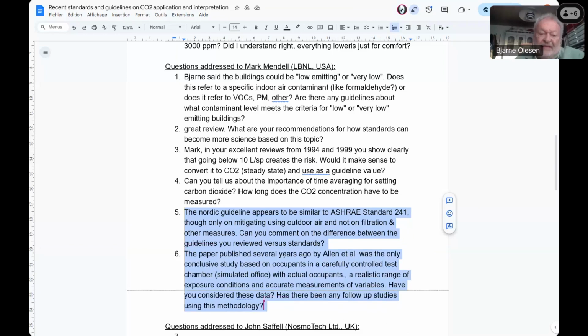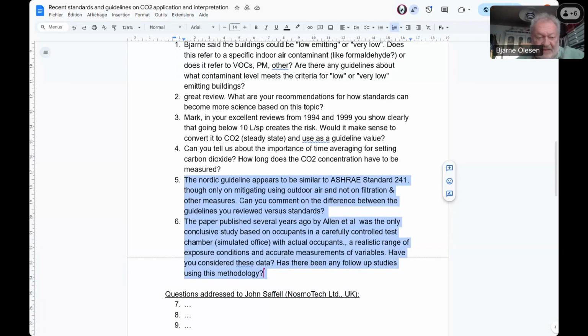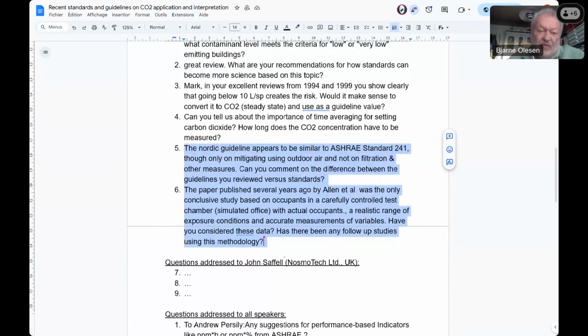Well, the ASHRAE standards are setting, like the standard for ventilation 62.1, a table where they specify what you should ventilate in case of a pandemic. The whole calculation background is not in the standard yet, but they are working on making a more complete standard where you can see how they got to the numbers. Now, the European method, which will be in the European standard I mentioned earlier in the revision, is coming up with a ventilation rate, but the two other measures, air cleaning and filtration, are also included. In the equation, there is a part which is dealing with air cleaners, and the third way of reducing the exposure is to reduce the number of people in the space, and that is also a possibility in these calculations.